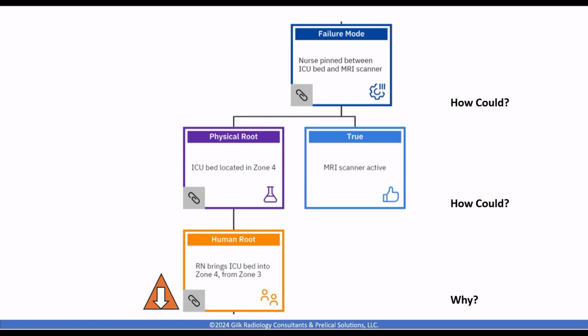All right, let's go down the bigger leg of this now, and it says the nurse was pinned, and I'm going to say, how could that happen? Well, the ICU bed had to be in zone 4, and the MRI machine had to be on. That's what I needed for that to happen. So I come down from there and say, how could the ICU bed end up in zone 4? Well, a nurse came in with that bed from zone 3. Now these are where it takes away the linearity argument, is that at this particular level here, we're going to say, well, why did the nurse bring the bed from zone 3 into zone 4?